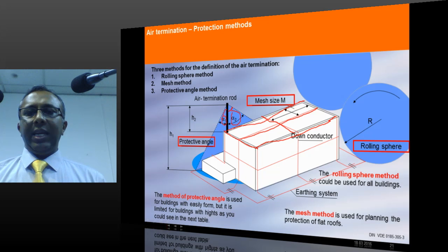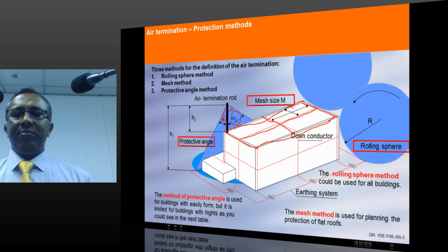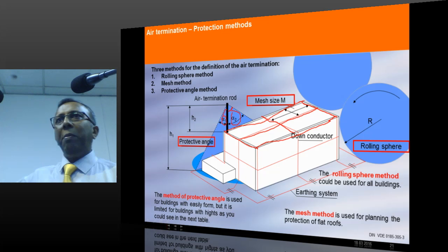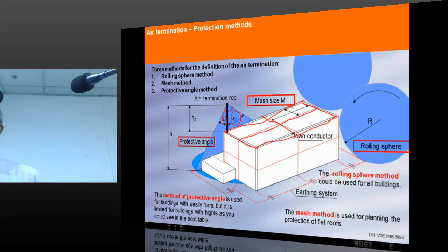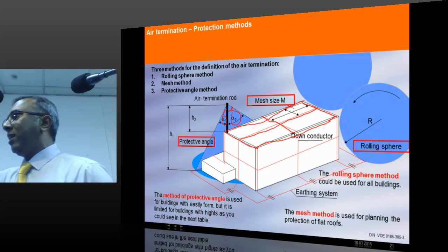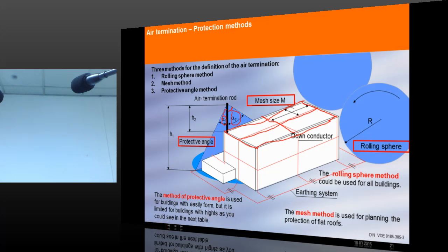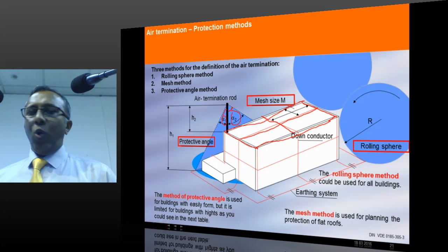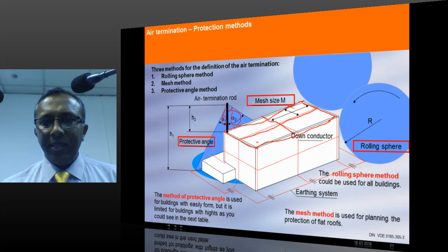So something like this, and the size of the mesh is explained in this standard. Remember, for any structure, any building, the most important points to be protected are corners and edges. So for the protection, air termination or down conductor, first we should always design the system in such a way that lightning will probably go to corners and edges. I don't want to explain why, but basically corners and edges are more important.